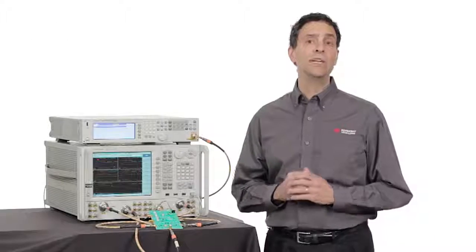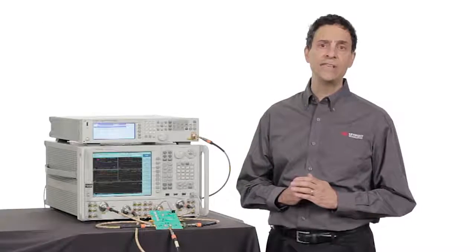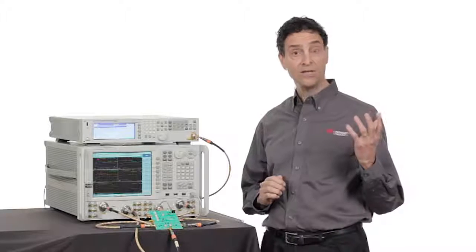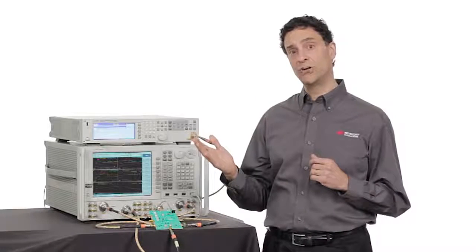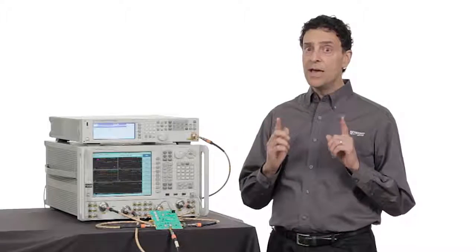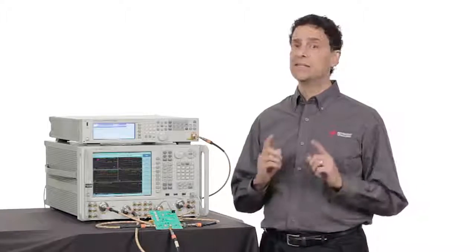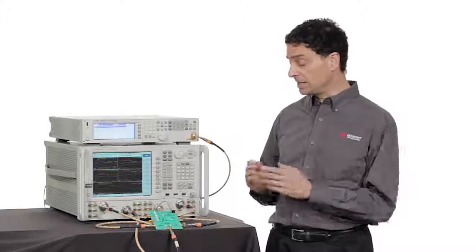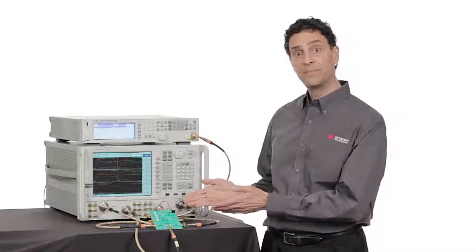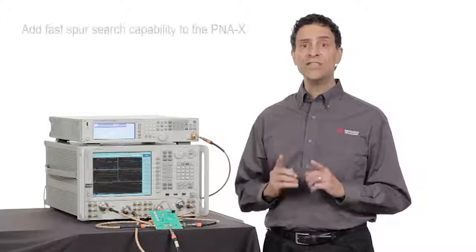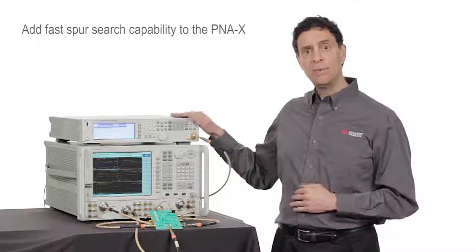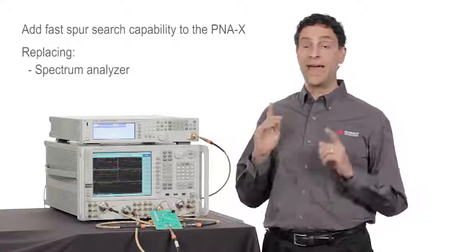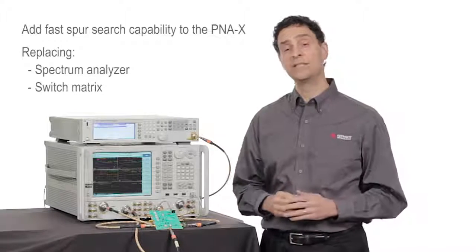These measurements can be performed many times faster compared to those done with the traditional approach using a spectrum analyzer and stand-alone signal generators. However, a spectrum analyzer remains an essential tool to measure undesired spurious signals coming from the converter. The new PNA option adds fast spur search capability to the PNA-X, replacing a stand-alone spectrum analyzer and switch matrix in your test systems.